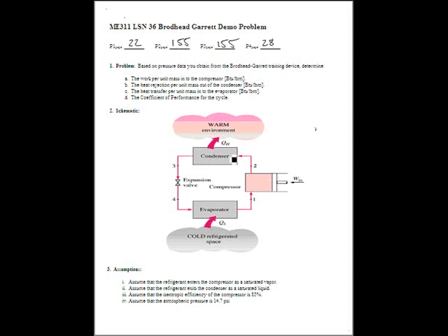Notice that the isobaric assumption is pretty good here, to state 3, where it goes from vapor to liquid, which we saw in the sight glass. It goes through our expansion valve and drops the pressure down to 28 psi gauge. We go through the evaporator, where we go from saturated mixture to vapor again. The assumptions we made are listed here, and this is also the worksheet on page 77 of 84.